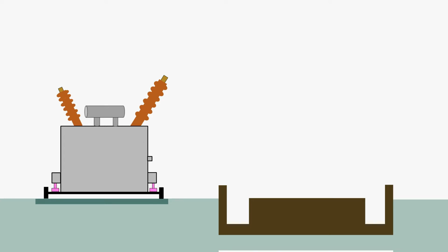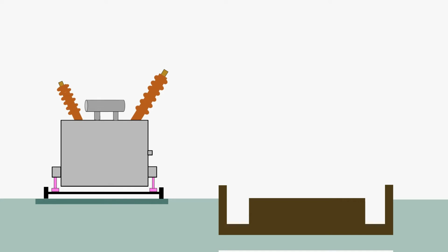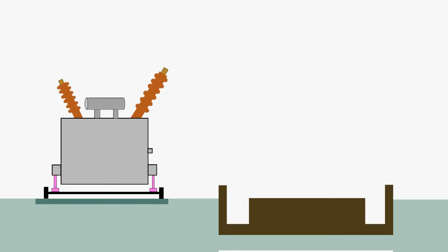We position the jack under each of the transformer's jacking points, whether four or six. Once the jacks are in position, we slowly raise the transformer. This is normally done in several steps, as it's impossible for a single jack to raise the transformer to the height that we require. So in stage one, we raise the transformer. Then we provide wooden supports beneath the transformer. We obviously need to make sure that the packing materials used can take the full weight of the transformer. Then release the jacks, raise them to a higher level, and finish off the raising operation.